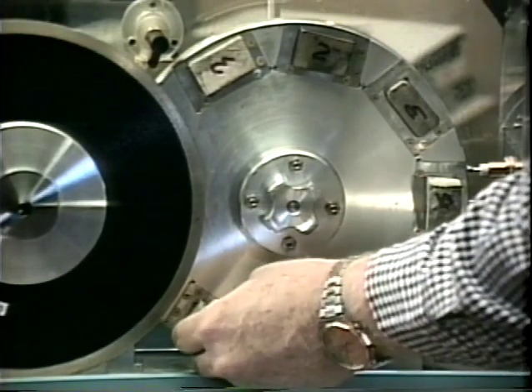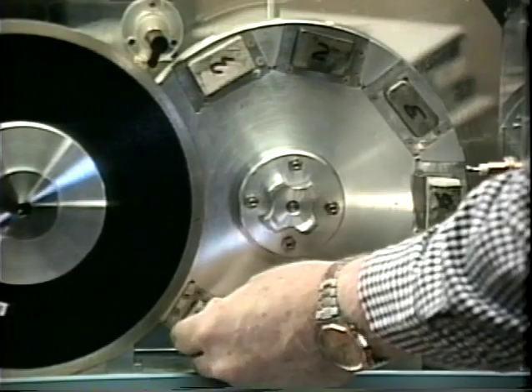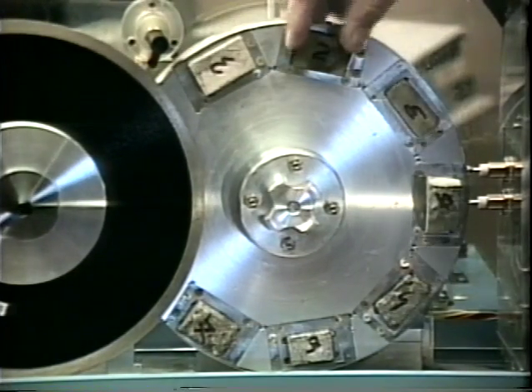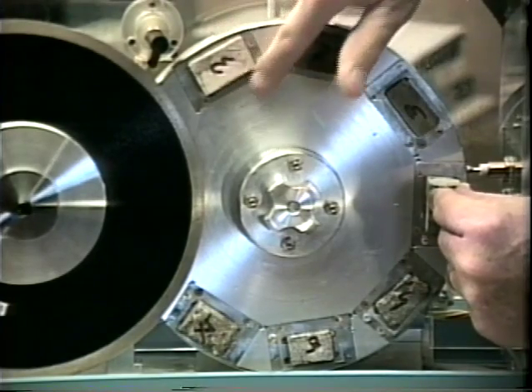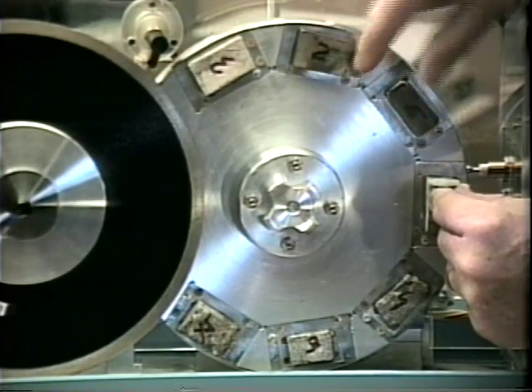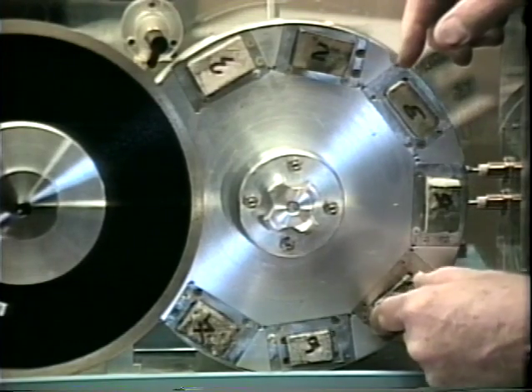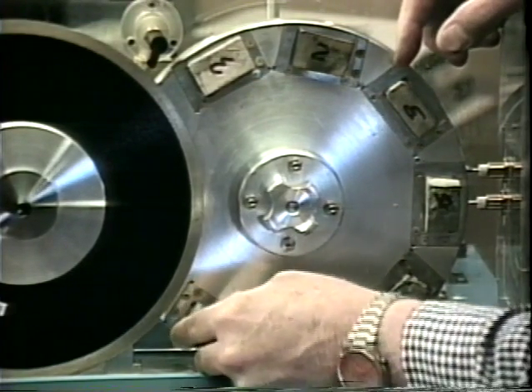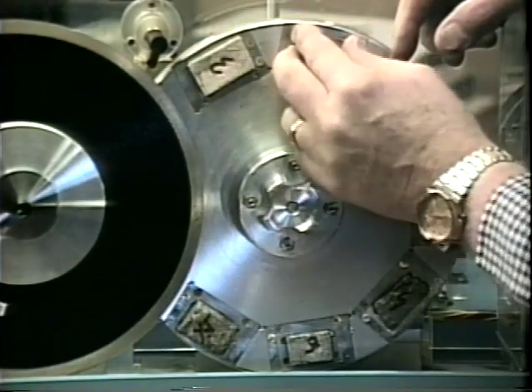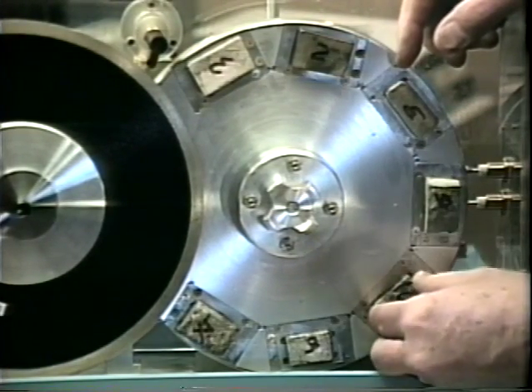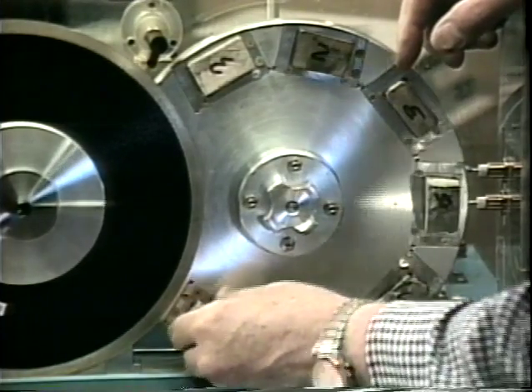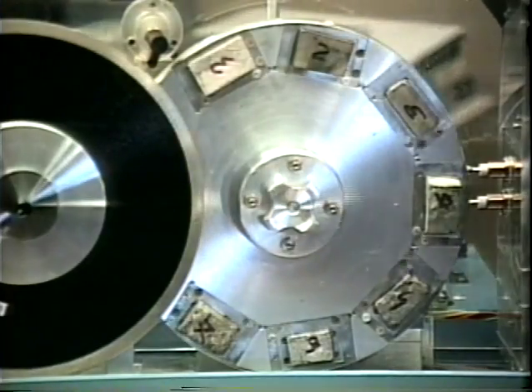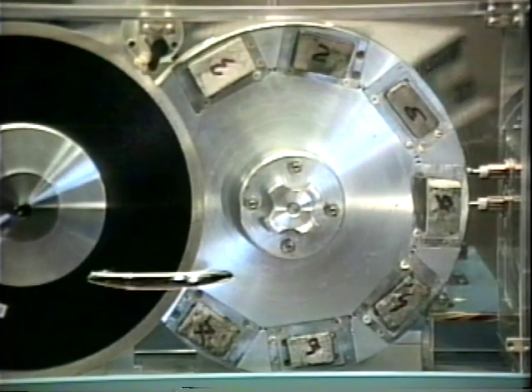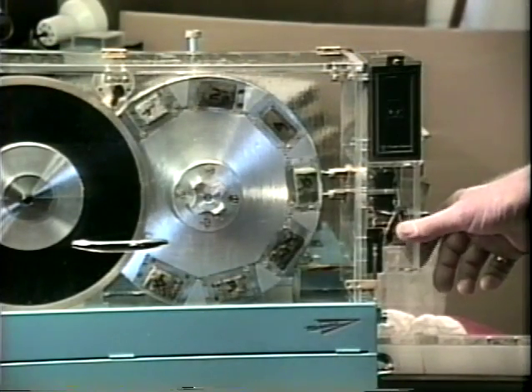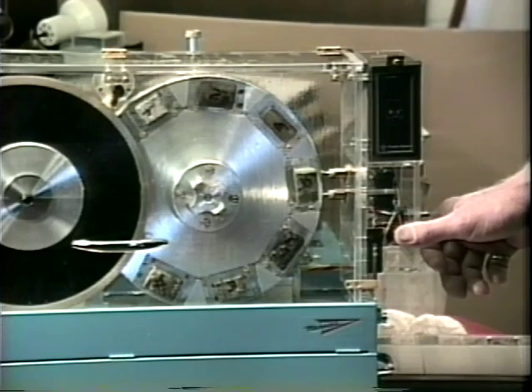Number 7, or the last specimen, loaded into the chuck, and we check the mountings to make sure that the specimens are against the stops, these little button locator stops, so that none of the glass slides are out of position. If they are, it could cause a leakage in the vacuum system. Next, we'll close the coolant shield door. We'll start the cycle by pulling the cycle manual switch forward.